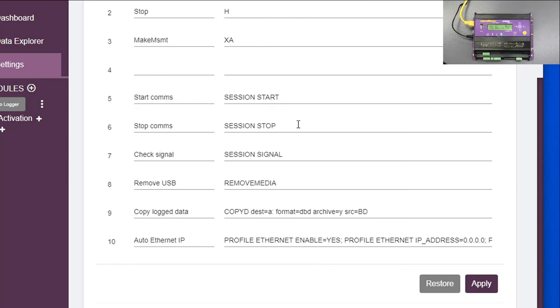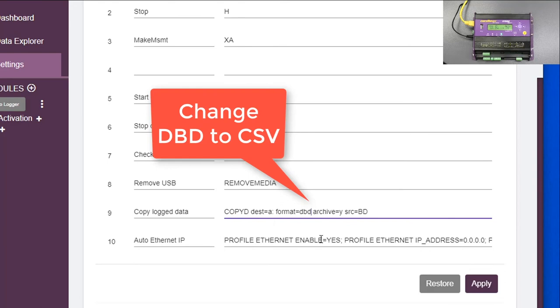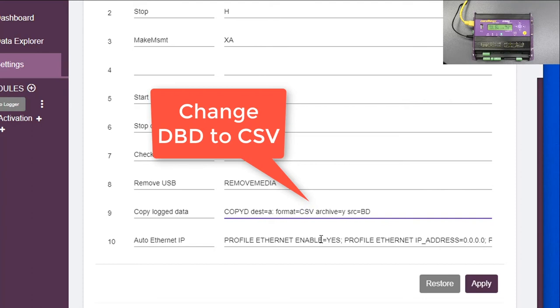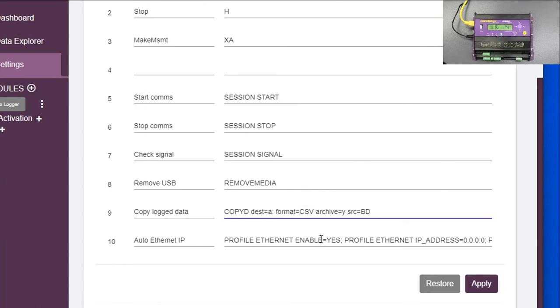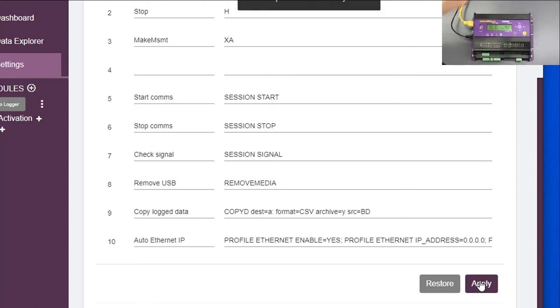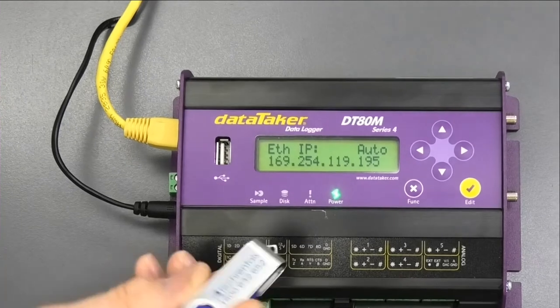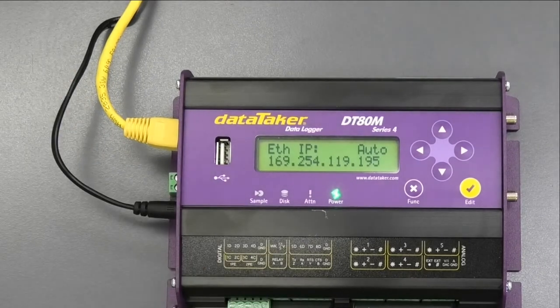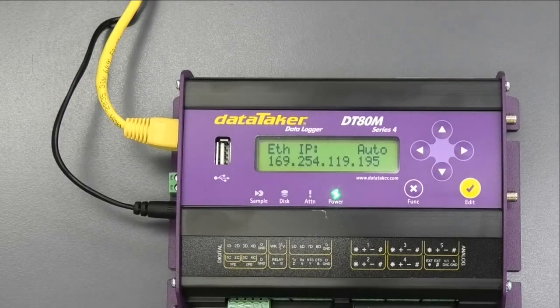The other thing that's worth doing on here is, if we scroll down here, that's right, this copy data. At the moment, if we want to use the memory stick to download, the format it will download in is DBD, which is the data-taker format. You're better off using CSV, because when you download in CSV, you can import it straight into Excel. So we make that CSV, uppercase or lowercase again. When you're using the memory stick to download, it's fairly simple. I'll apply that now.